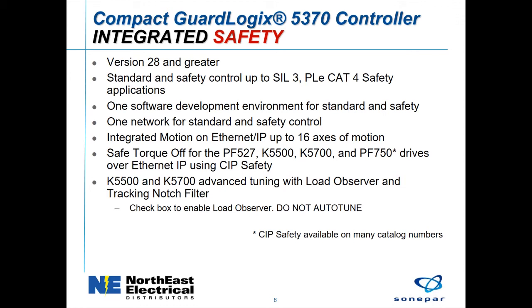And then for the Kinetix servos, the 5500s and 5700s, there's an advanced tuning feature called Load Observer and a tracking notch filter that are available. This basically gets rid of the old auto tune. You check a box, there is no tuning required. All you need to do is commission the drive, make sure that it runs the right direction. Other than that, you do not have to do any auto tune. One caveat is not all models of drives are CIP safety, so you need to be aware of that when you're ordering the drives, that you're ordering something with CIP safety if that's what you want to use.